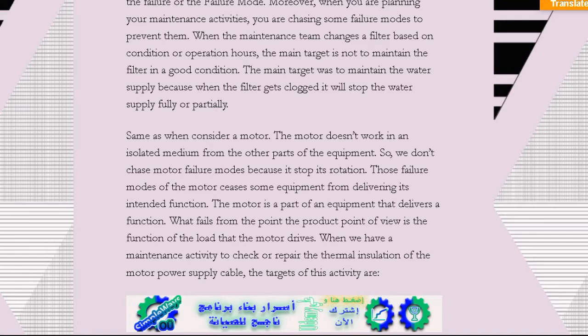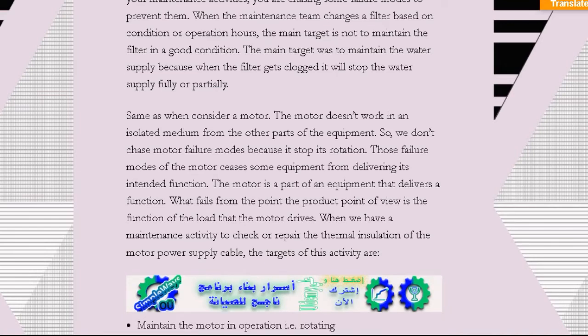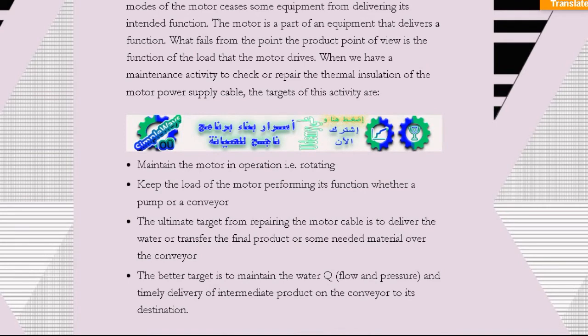So why did the pump stop? Because the motor stopped. Why did the motor stop? Because the pump was overloaded. Why was the pump overloaded? Because the bearing is jammed. So bearing jam, or bearing was having a problem, or coupling was having a problem, something like that, caused the motor to trip, and that caused the delivery of the water to stop. So we need to be specific in the failure mode to some part that we are going to repair.